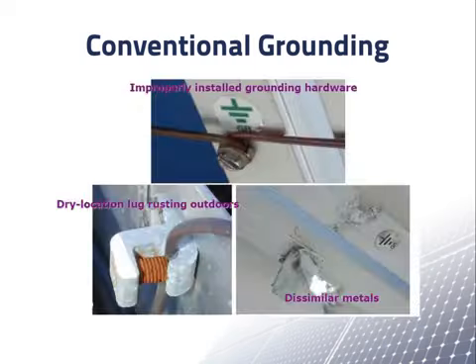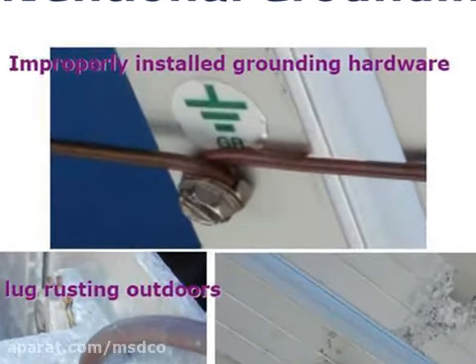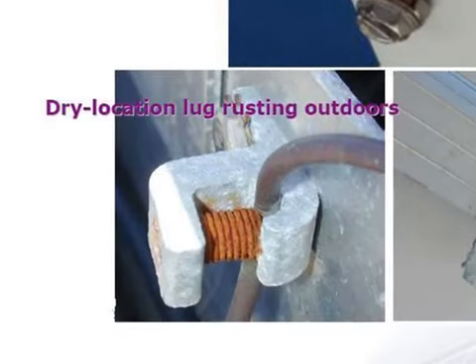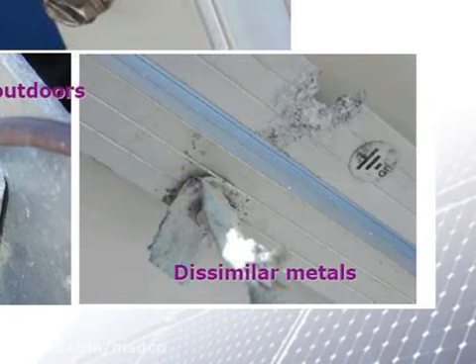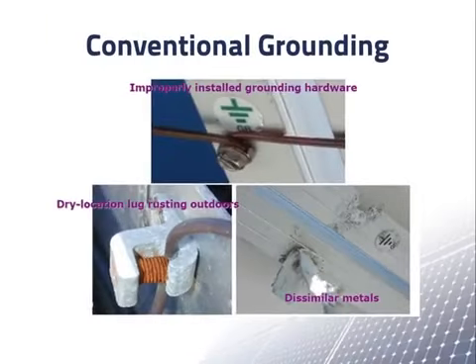If you talk to any PV system inspector, he will have a collection of pictures of grounding mistakes. Here are a few. At the top, we see an improper connection between an equipment grounding conductor and the aluminum frame of a module. It looks like this installer simply took a bolt and washer, which are not intended for a ground connection, and used them to connect the frame and the wire. At the bottom left, we see a lug that was intended for indoor use, which corroded outside on a PV array. At the bottom right, we see corrosion that contact with the copper wire caused in an aluminum frame.